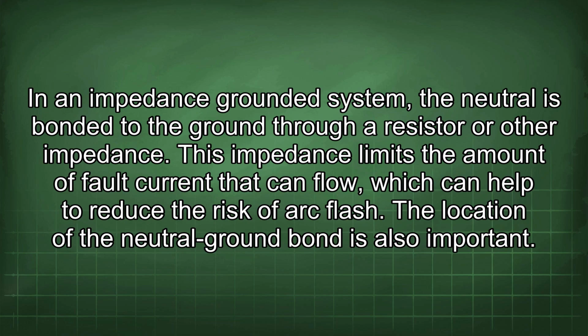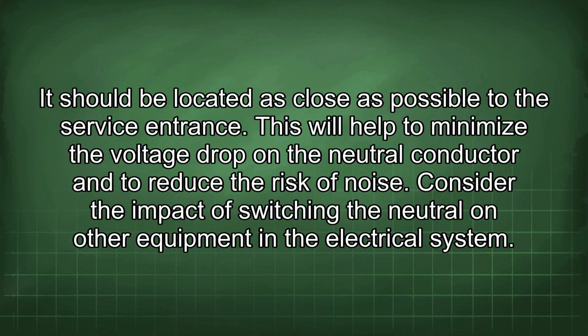The location of the neutral ground bond is also important. It should be located as close as possible to the service entrance. This will help to minimize the voltage drop on the neutral conductor and to reduce the risk of noise.